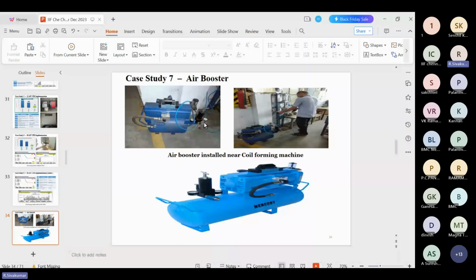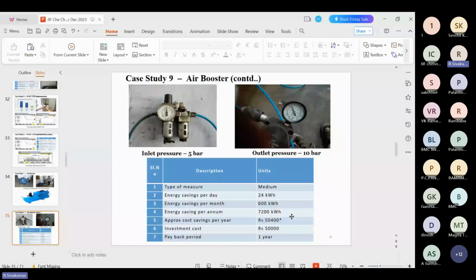Now 2 coil forming machines are operated with the help of this air booster. See, this is the air booster diagram. The air booster itself has a 50-liter reservoir capacity. After adapting this air booster, the pressure generation is reduced to 7 bar. Due to this, almost 7,200 units per year were saved, and the cost saving is 50,400 rupees, with an investment cost of 50,000. So the payback period is excellent. This is the inlet pressure, and this is the outlet pressure. Inlet pressure is 5 bar, outlet pressure is 10 bar. If this inlet pressure is given to the air booster, it generates 10 bar.